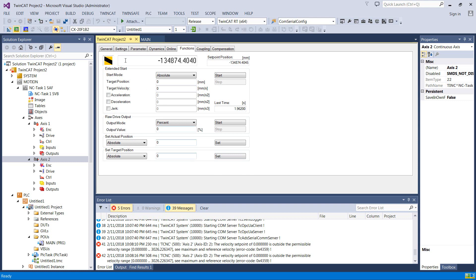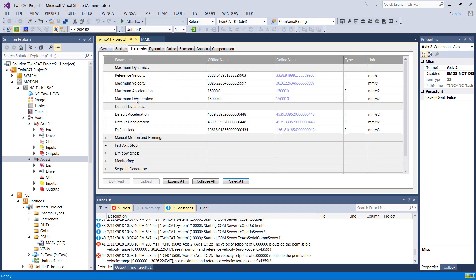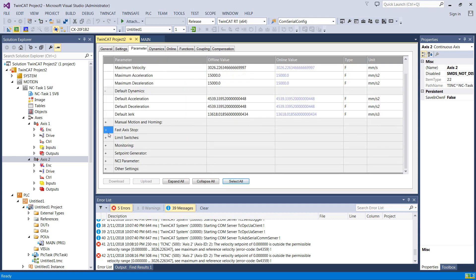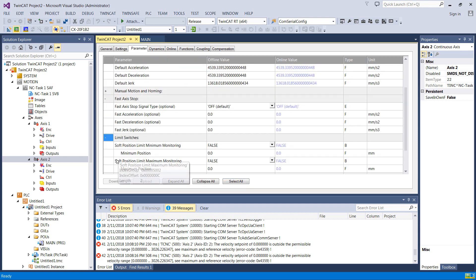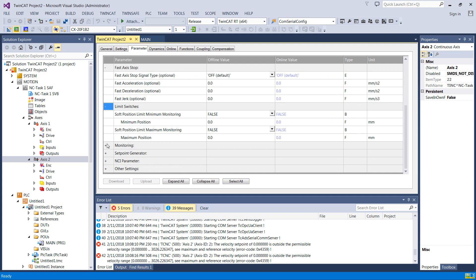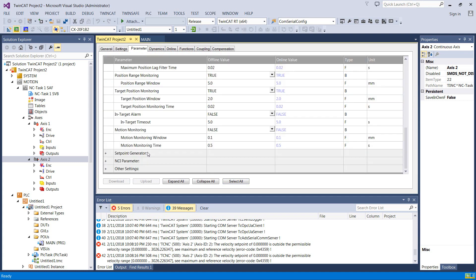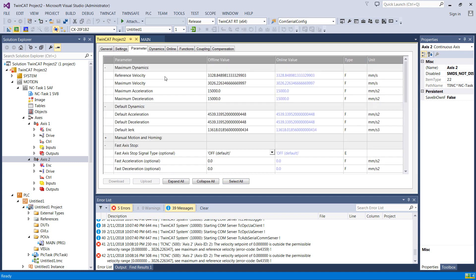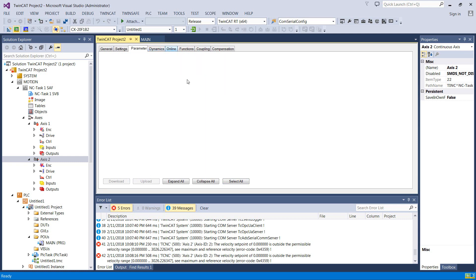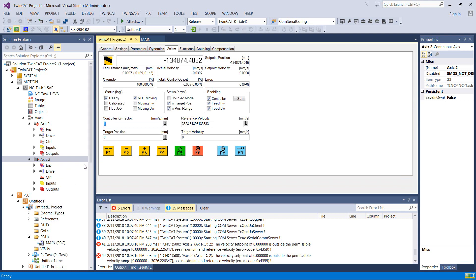But there's just a ton of settings in here, in these parameters rather, that, you know, limits and stoppages and monitoring and just all kinds of stuff that you can set up in addition to what would be in the drive. So this is all at the NC level, whereas the other settings we were in for the drive were at the drive level. So you can close the servo loop here on the NC side. You can close it on the drive side. You can do all kinds of different stuff. So we're going to kind of just go about getting the system working with changing as little as possible for now. But otherwise, this is a functional system here. So we'll move over to the PLC here shortly.